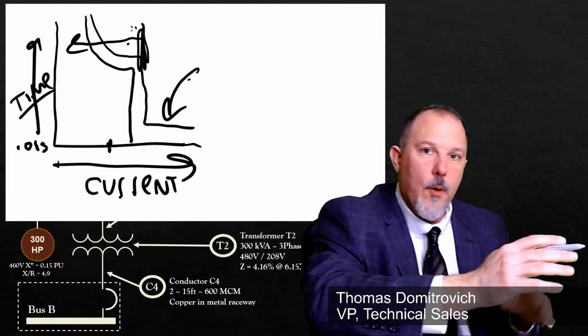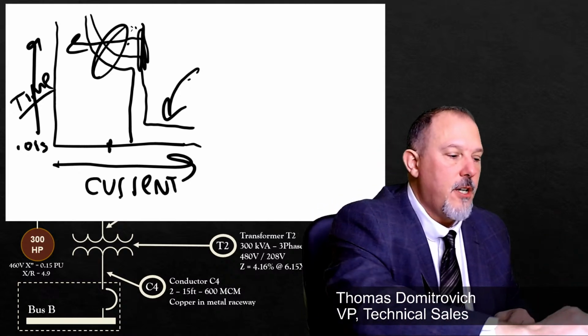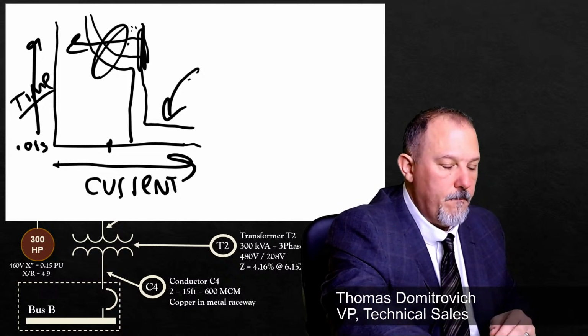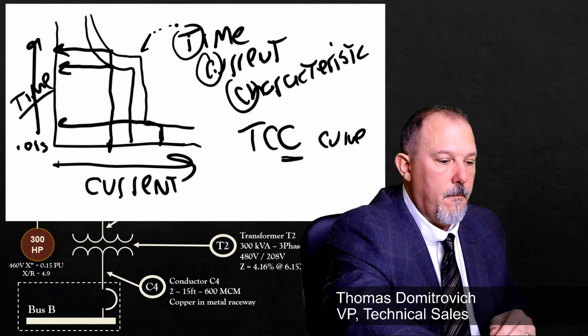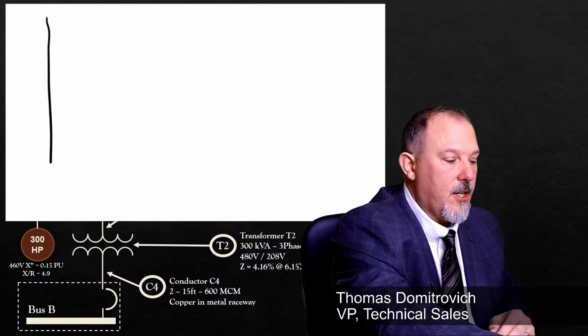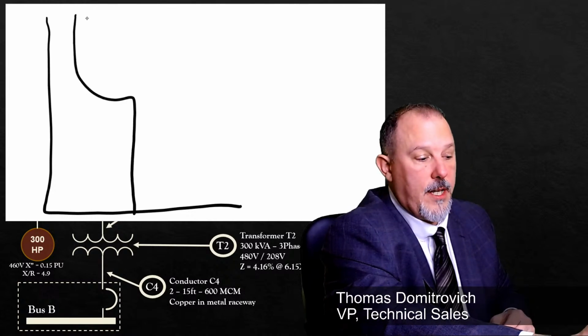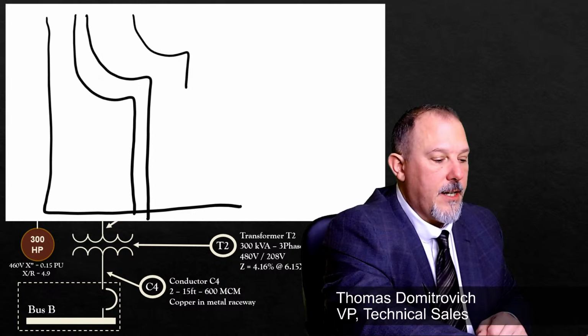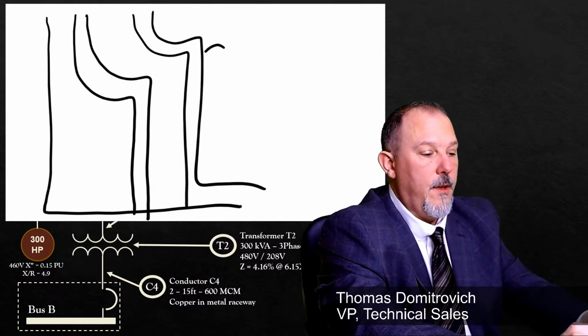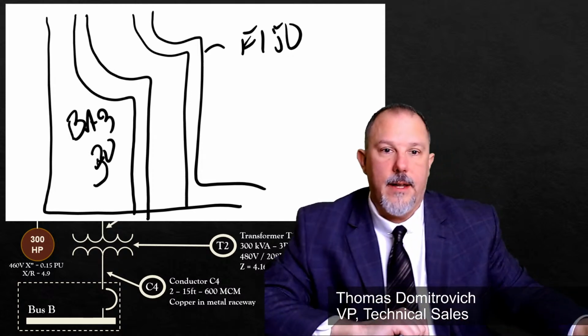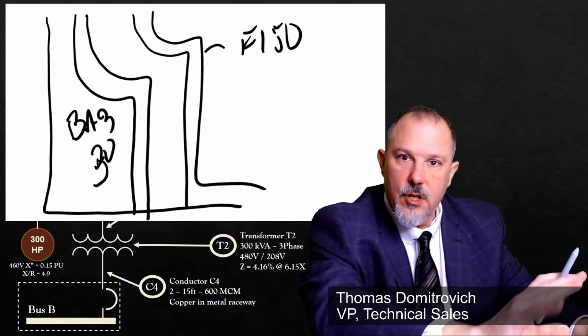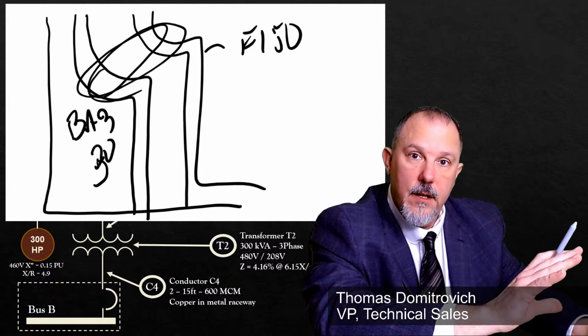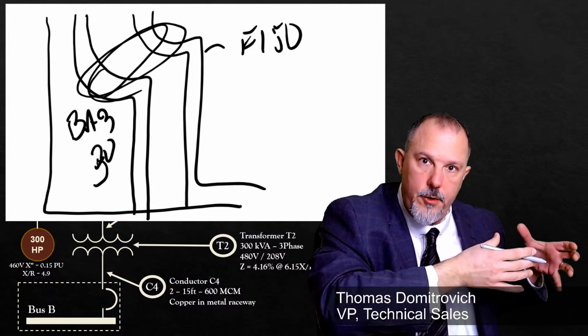when we say overloads, when we're talking selective coordination, what we're talking about is this region of the curve. So I could, for example, have a TCC curve that has a molded case circuit breaker downstream, which is a BAB, and I could have an F150 upstream. So this is the F150, and this is the BAB 30. Can't write with this thing, but in any case, I have two circuit breaker curves. What you want to make sure is that you don't have an overlap in your curves in this region. And that's why in the definition we say from overload to short circuit, and your short circuit is going to be probably up in that region.